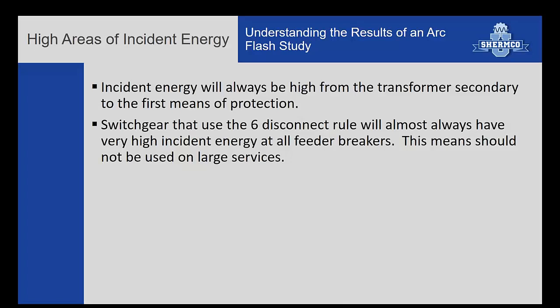Similarly, we see high incident energy in commercial buildings that have the 6 disconnect rule. We'll see where they use one piece of gear but no main. They feed the building, and then they have 6 disconnects that feed the building. Those are almost always high incident energy.